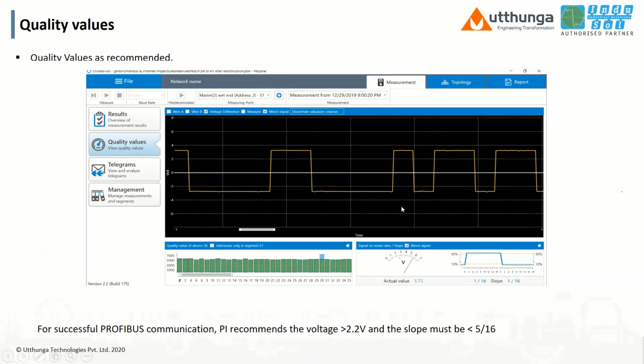How is the oscilloscope? Is there any disturbance in the network? These things I can understand. And also you can see what the voltage is and also the slope. As PI recommends, voltage should always be 2.2 volt and slope should always be less than 5/16. So we need to analyze the plant to understand whether your PROFIBUS nodes or network is in standard, and whether it is running in a good or stable condition.